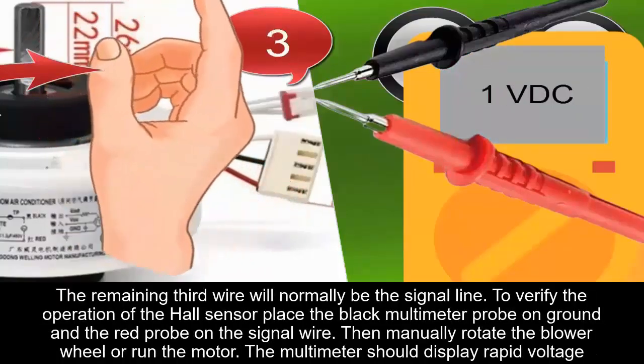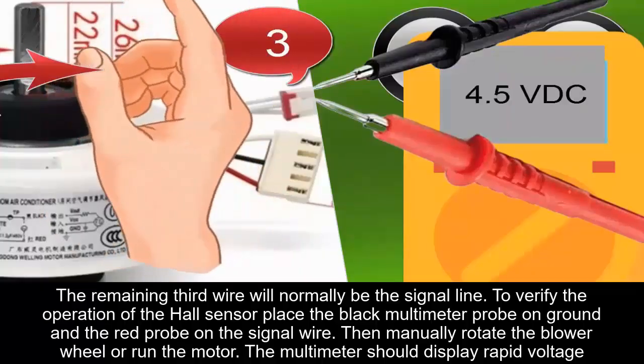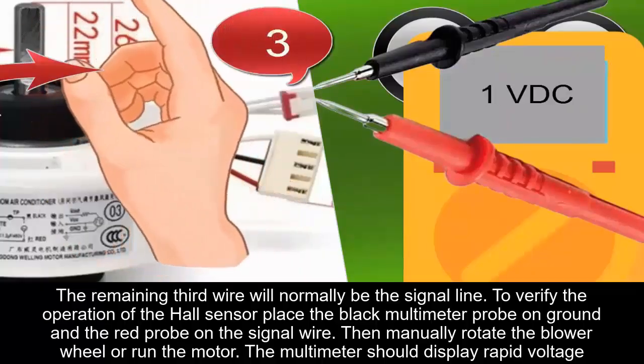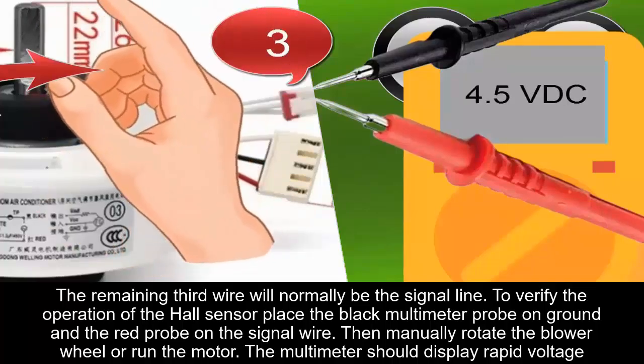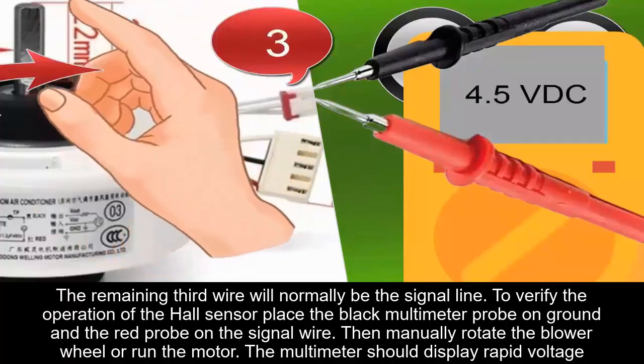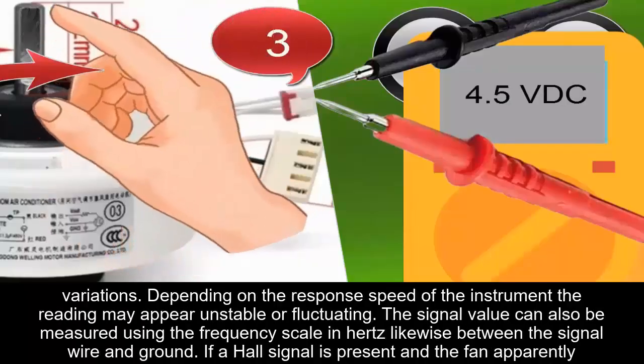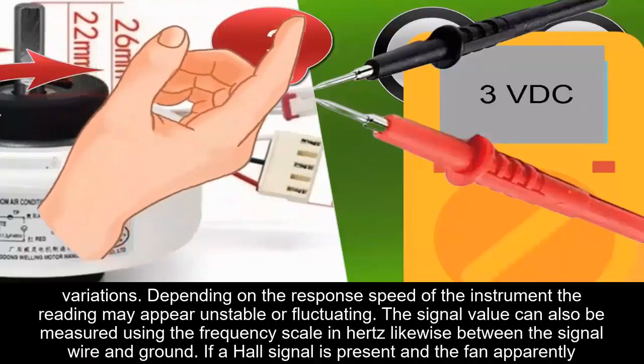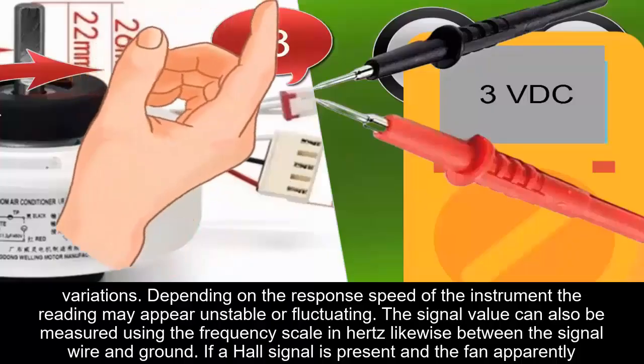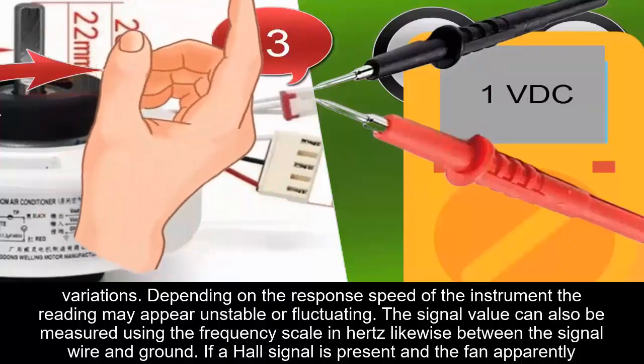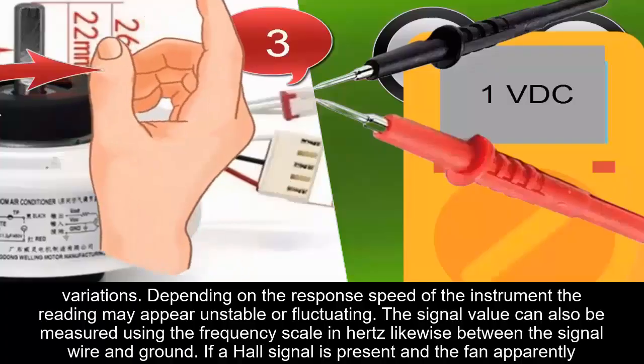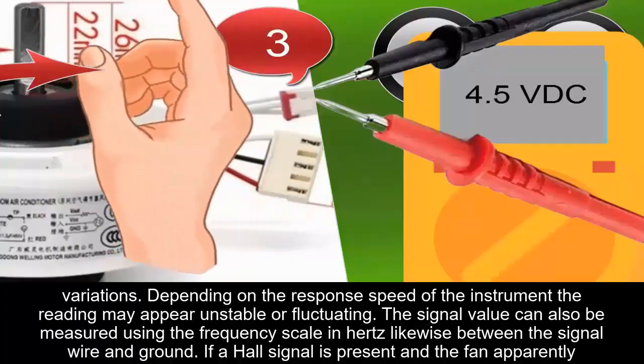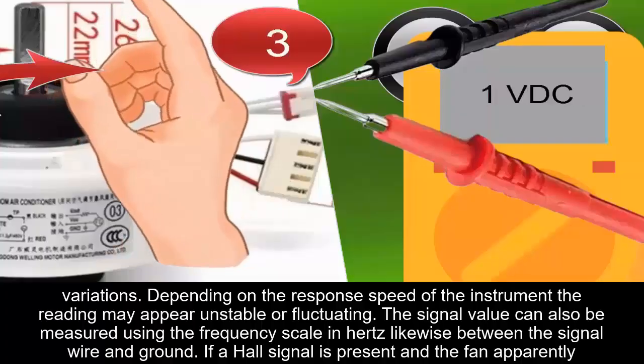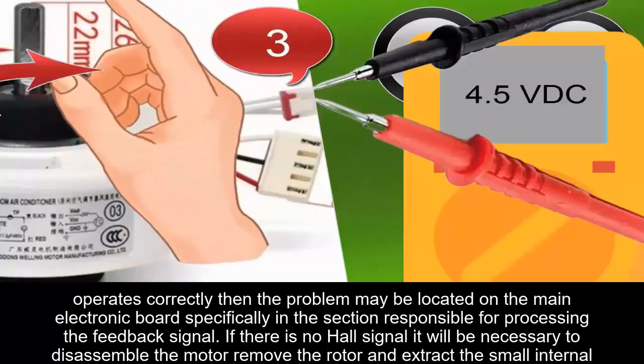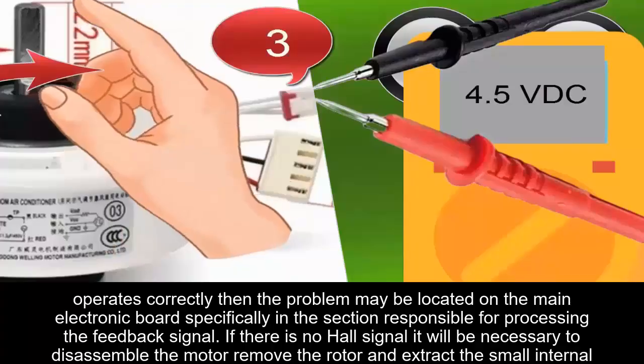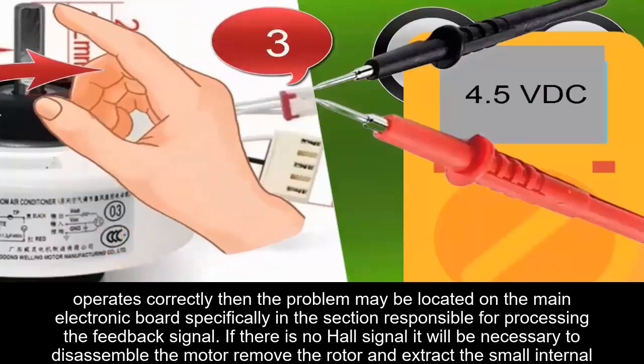To verify the operation of the Hall sensor, place the black multimeter probe on ground and the red probe on the signal wire. Then manually rotate the blower wheel or run the motor. The multimeter should display rapid voltage variations. Depending on the response speed of the instrument, the reading may appear unstable or fluctuating. The signal value can also be measured using the frequency scale in Hertz, likewise between the signal wire and ground. If a Hall signal is present and the fan apparently operates correctly, then the problem may be located on the main electronic board, specifically in the section responsible for processing the feedback signal.